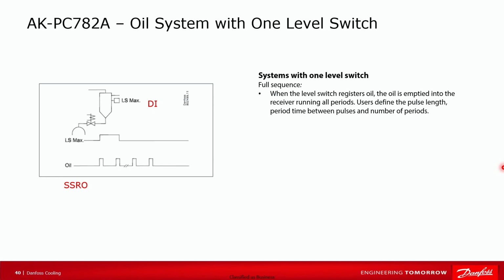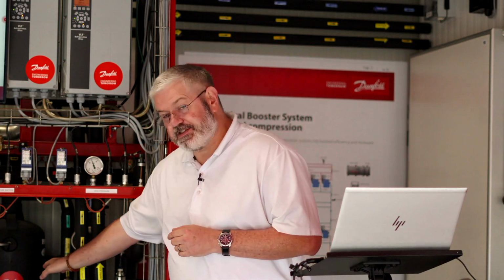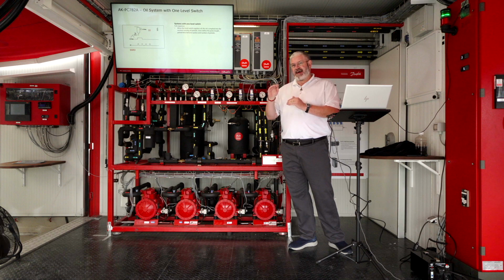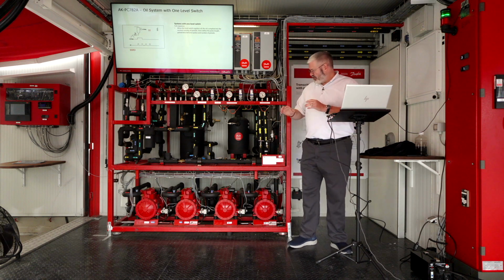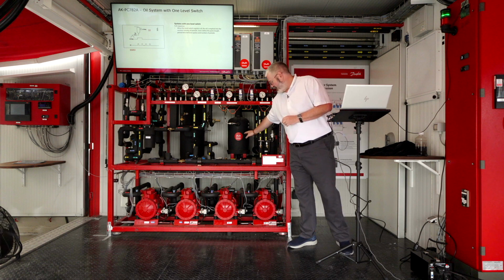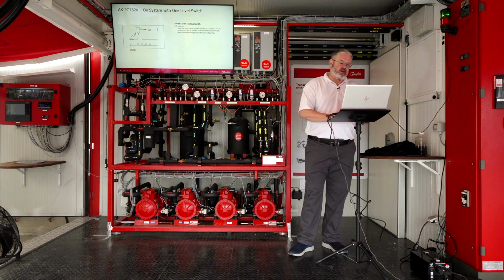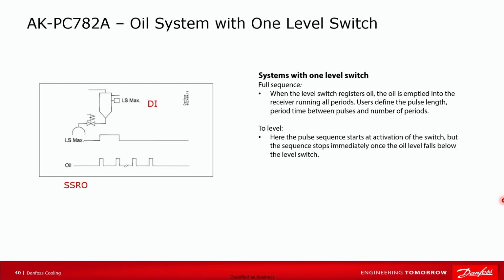There's 3 control methods in our pack controller. The first one would be a system where this reservoir has just one switch, which is a high level switch. So all the control is going to be done based around the level of oil in your oil reservoir. On a system with a single switch, it's going to be a high level switch, and basically when that switch trips, you know that the oil reservoir is full. So we're going to activate what we call an emptying sequence. That trips, and then we start pulsing the oil solenoid with a solid state relay output. On the pack controller, two of the relays are solid state.